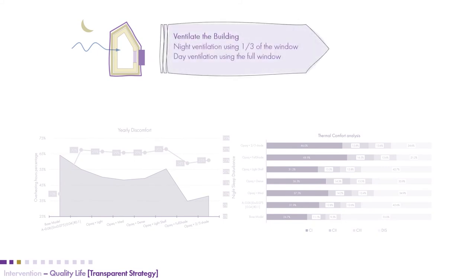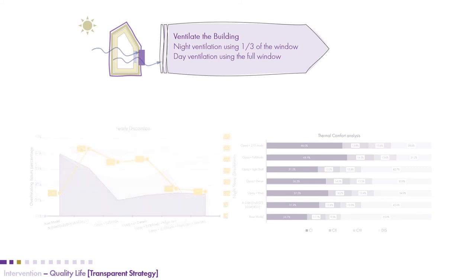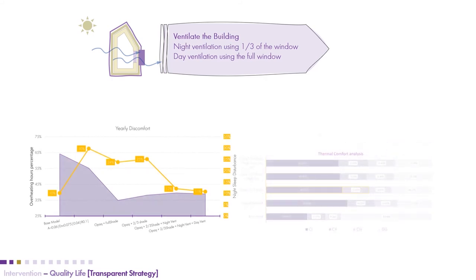Next we tested the ventilation of the building. For natural ventilation at night, we assumed only one-third of the window would allow ventilation, while during the day the whole window would be open. This had a very drastic positive effect on night cooling, night sleep discomfort, and daytime comfort. We noticed that ventilation was a very key factor in improving the thermal comfort of the building.